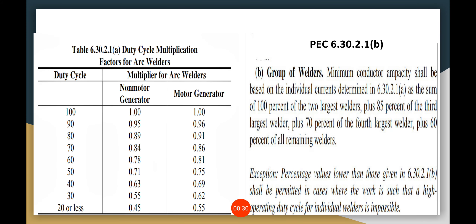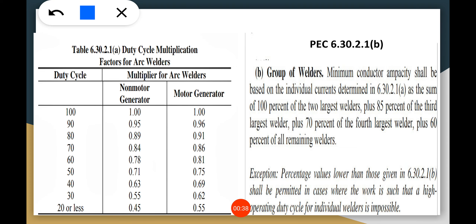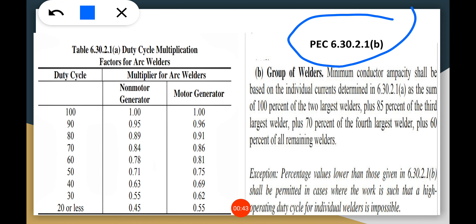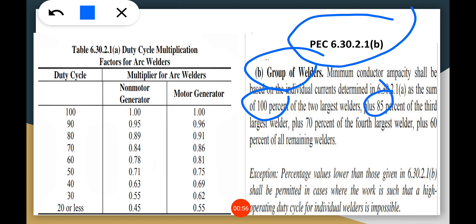These are the PEC tables we are going to use as reference. Table 630.2.1(a) is the duty cycle multiplication table, and Table 630.2.1(b) is for the group of welders. It has percentages: the first two largest welders are at 100%, the third one is 85%, the fourth is 70%, and the rest will be 60%. This also applies to the duty cycle whether it's a non-motor or motor generator.